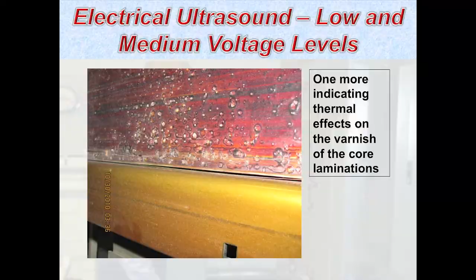Because this miter joint, they fit these core pieces nice and snug. They bond them, varnish them, bolt them together, bake them in the oven to ensure a good bond so they can't separate. But it says here that the miter joint connecting the center phase of the horizontal laminates is no longer connected properly because that B phase is bowing out. It's hard to see in these pictures, but it was literally offset by about a quarter inch. It was horrible, and unless you pulled back the varnish shield, you never saw it.